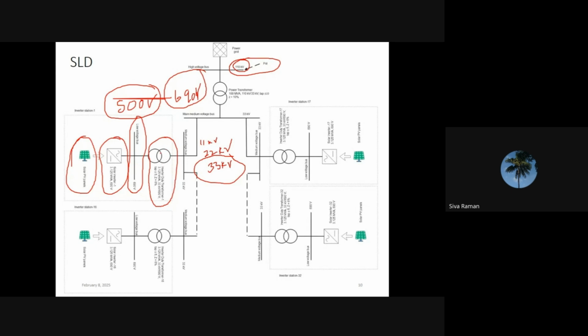So this transformer will step up the voltage from 690 volt to 33 kV, and it will be connected to the main transformer. This is the main transformer in a solar plant, a 110 or 33 kV transformer. Typically this connection is called the collector network. For a large scale plant, we have a large number of inverters. For example, for a 100 megawatt plant, if you are using a 2 megawatt inverter, we have 50 numbers of 2 megawatt inverters. We have to connect all 50 inverters to the main 33 kV bus at the substation. For that, this collector network will be used.